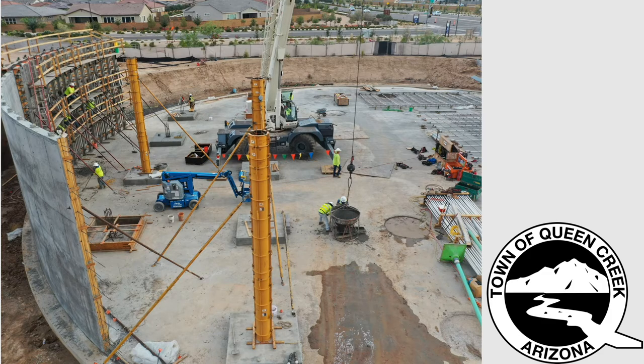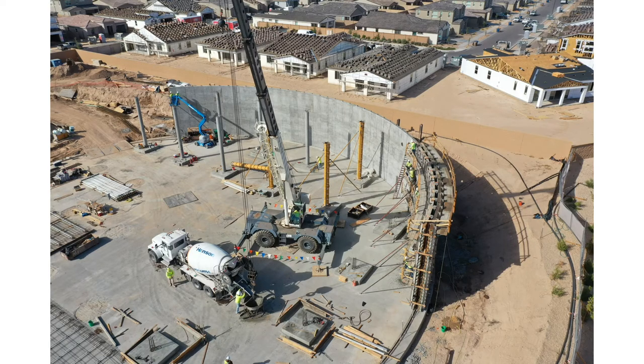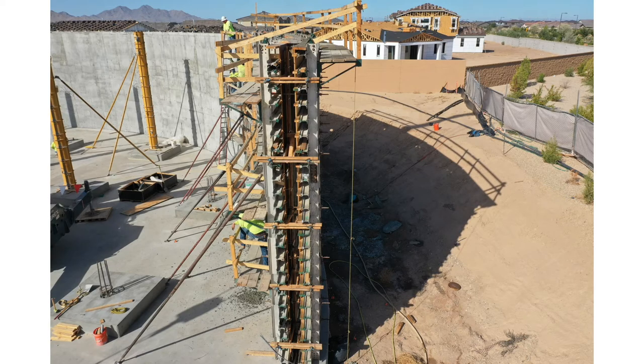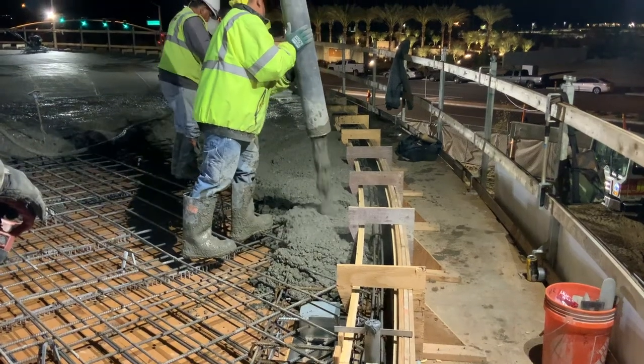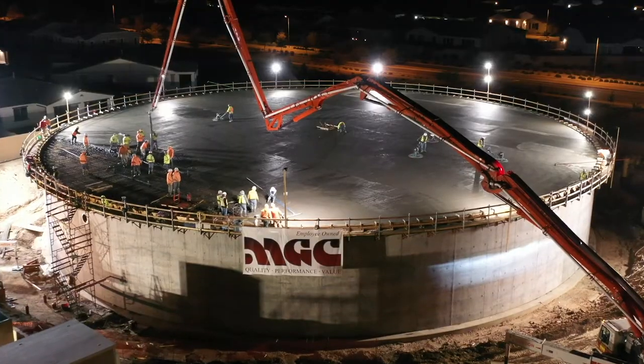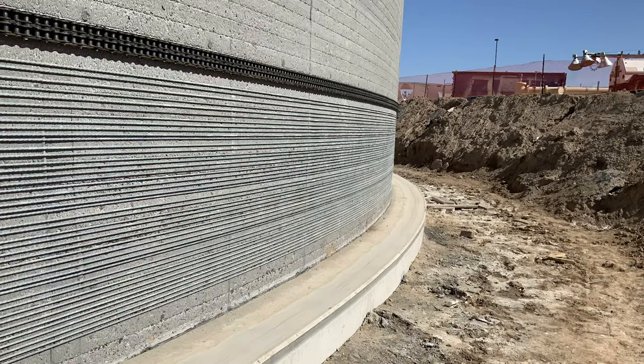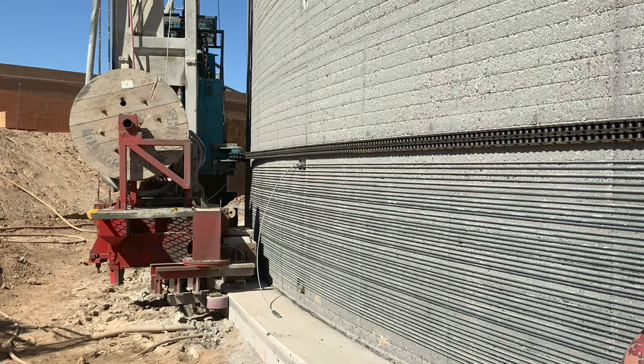There are 122 sets of seismic cables constructed of galvanized steel running from the foundation into the walls, allowing the walls to rotate slightly independent of the foundation during a seismic event. They are the only true connection between the foundation and the walls. The third phase of the concrete was for the roof, completed in one continuous pour with 630 yards of concrete. The tank is wrapped with approximately 66,000 feet of steel cable — roughly 12 and a half miles — with an applied force of 14,950 pounds, covered by 60 cubic yards of shotcrete.